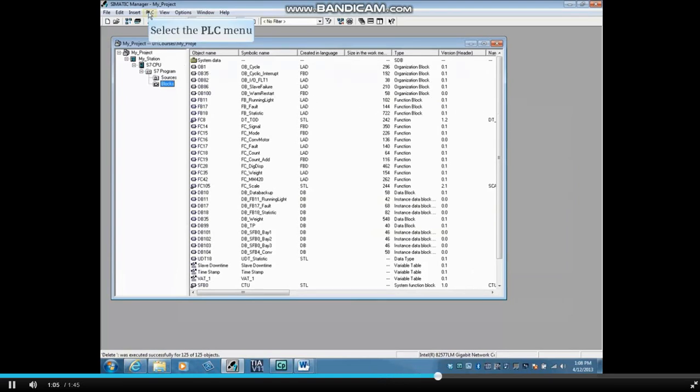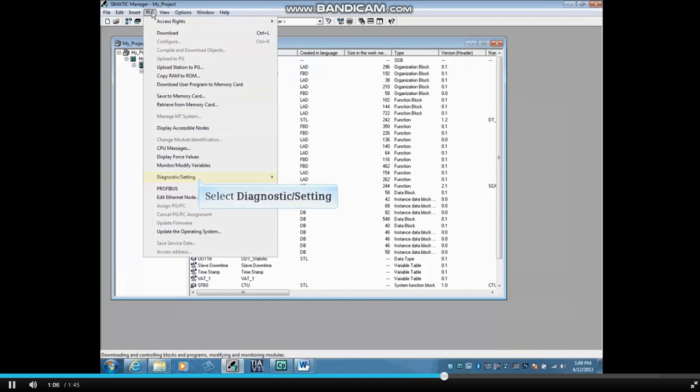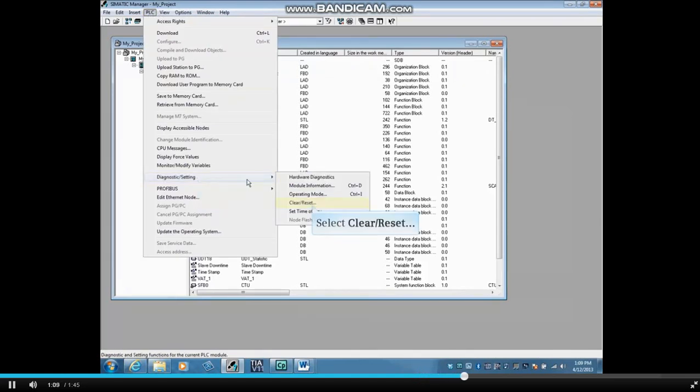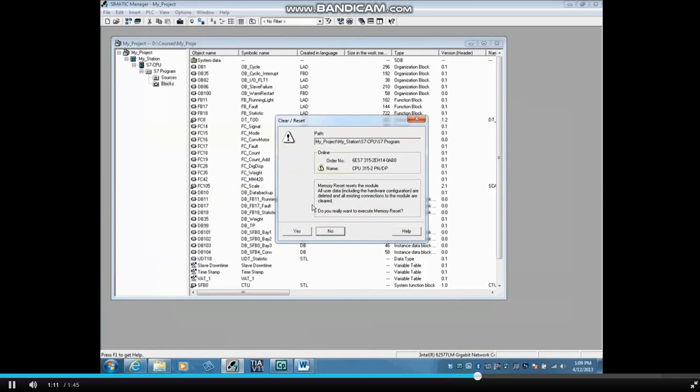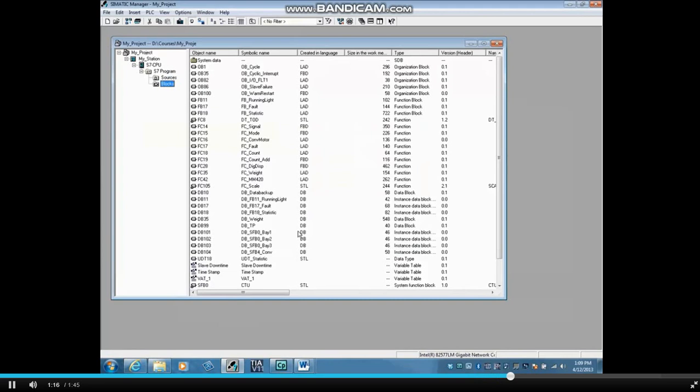Click the PLC menu. Click Diagnostic Setting from the Context menu. Click on Clear Reset. Click Yes to the Clear Reset warning. This will also put the CPU in the stop mode. The micromemory card and CPU's RAM have both been cleared.